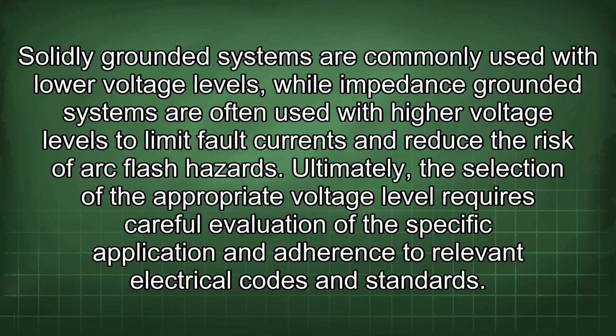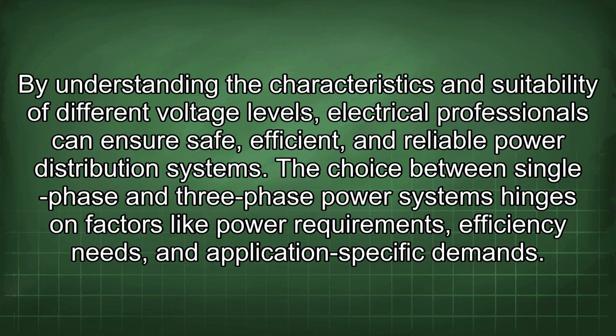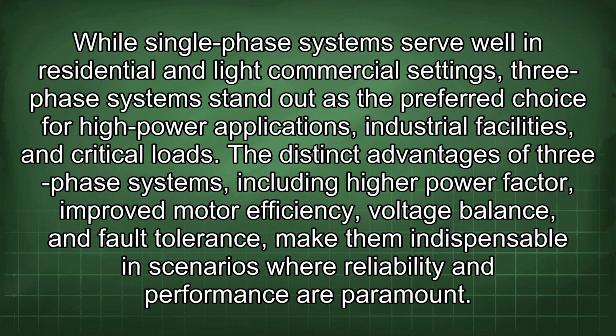Ultimately, the selection of the appropriate voltage level requires careful evaluation of the specific application and adherence to relevant electrical codes and standards. By understanding the characteristics and suitability of different voltage levels, electrical professionals can ensure safe, efficient, and reliable power distribution systems. The choice between single-phase and three-phase power systems hinges on factors like power requirements, efficiency needs, and application-specific demands. While single-phase systems serve well in residential and light commercial settings, three-phase systems stand out as the preferred choice for high-power applications, industrial facilities, and critical loads. The distinct advantages of three-phase systems, including high power factor, improved motor efficiency, voltage balance, and fault tolerance, make them indispensable in scenarios where reliability and performance are paramount.